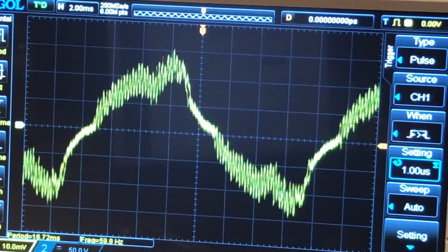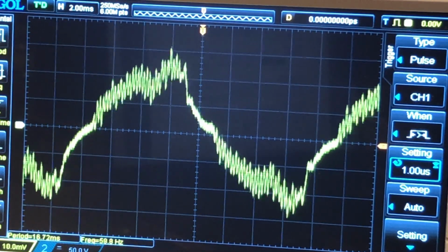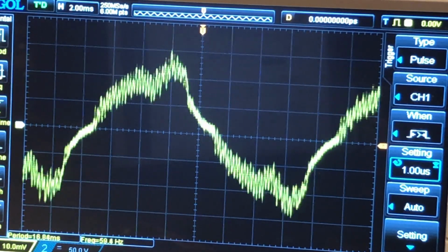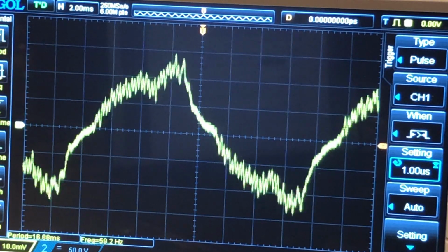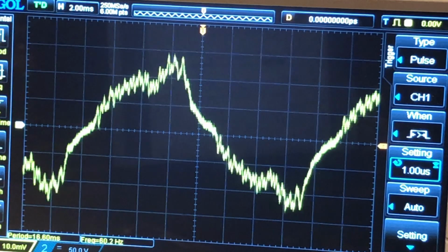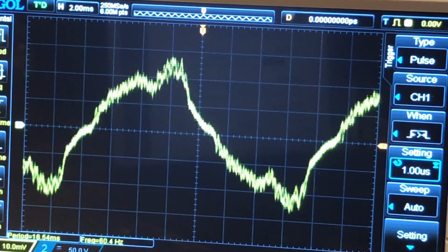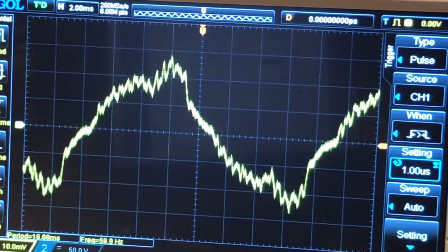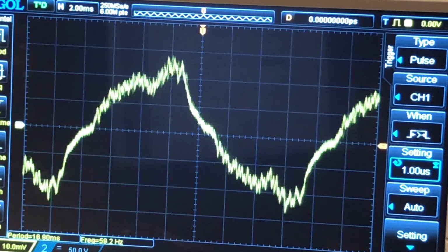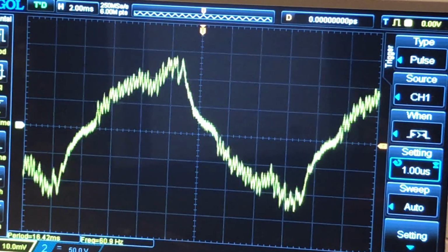Source selection. Press source to open the signal source list: channel 1, channel 2, or external. For the details, please refer to the introduction on trigger source. The current trigger source is displayed at the upper right corner of the screen. Select the channel with signal input as trigger source to obtain stable trigger. Pulse condition.